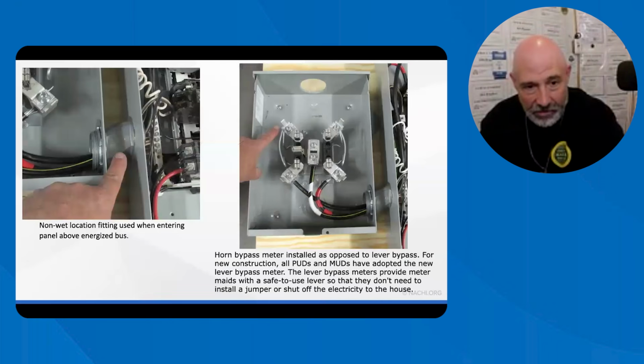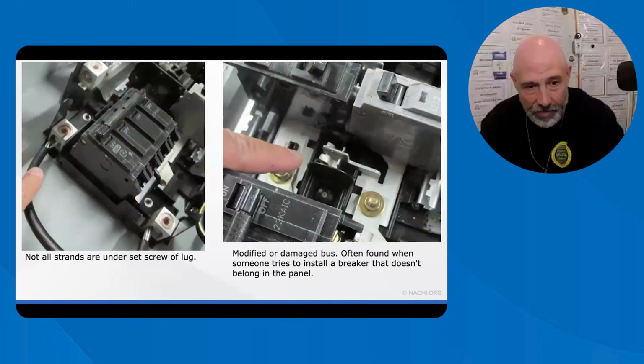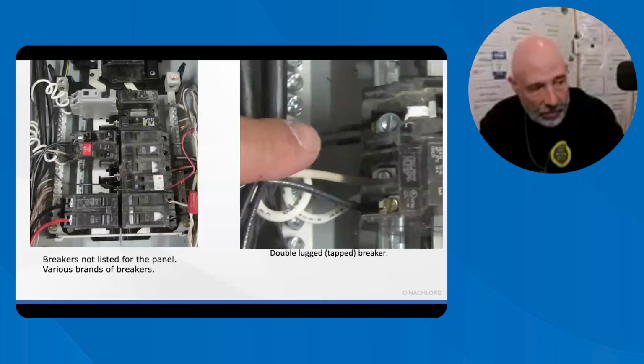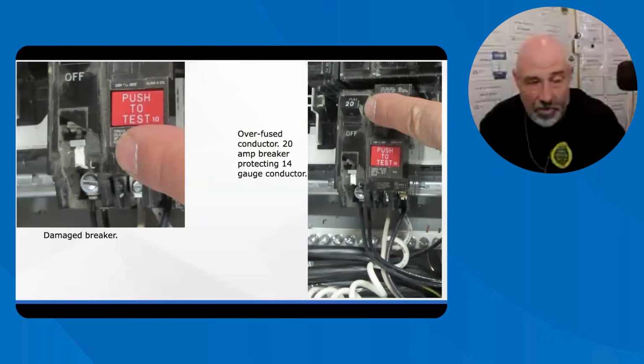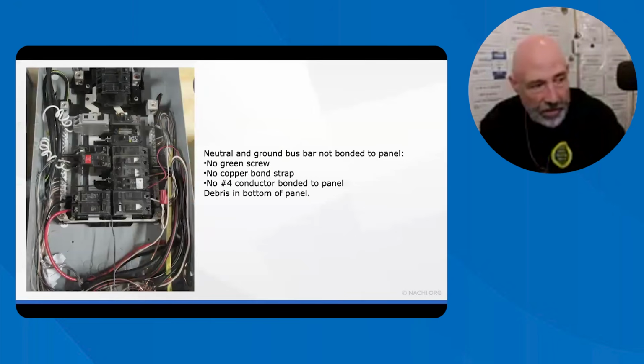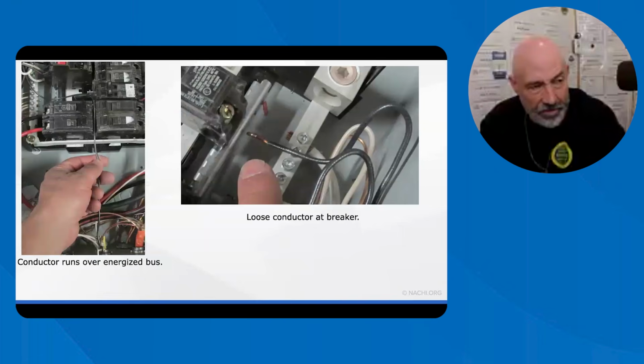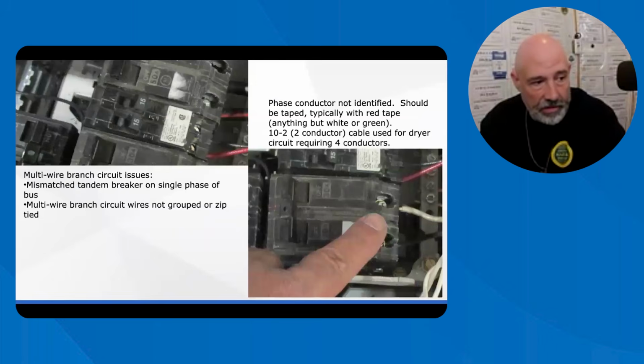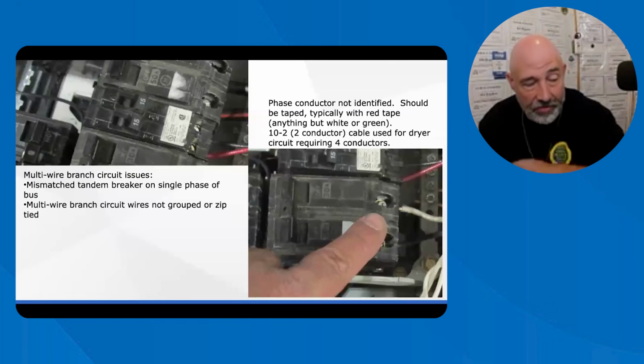Non-wet locations, kind of skip through here. I've seen this too. A straggler is what we used to call them. We don't want to see that, so make sure all strands are underneath those lugs. If you see any bus bar that is bent or corroded, make sure you call those out too. Same thing with breakers that are not listed for the panel. I'm kind of weirded out on that, so I'm not even going to talk about it right now. Test to push, that's what I've already told you. We're going through a lot of the stuff we already talked about. Any abandoned or disconnected wires, you might want to call those out. Same thing with multiple-wire branch circuits. If you see double taps, things like that, we've already talked about this.